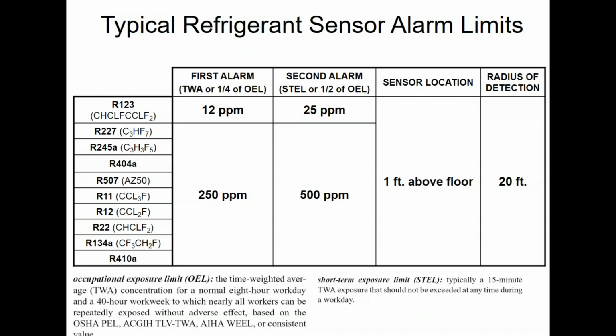Other refrigerants have different alarm points. I know some chillers are 123. I don't know why you buy those ones, but if you did, those have a lower alarm point because the refrigerant is a little bit more hazardous. So their occupant threshold is 12 parts per million.